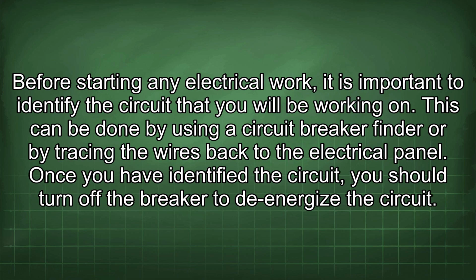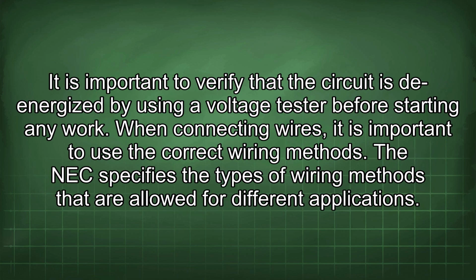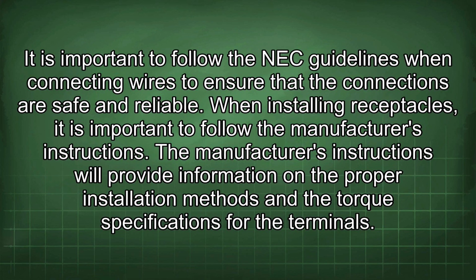Once you have identified the circuit, you should turn off the breaker to de-energize the circuit. It is important to verify that the circuit is de-energized by using a voltage tester before starting any work. When connecting wires, it is important to use the correct wiring methods. The NEC specifies the types of wiring methods that are allowed for different applications. It is important to follow the NEC guidelines when connecting wires to ensure that the connections are safe and reliable.